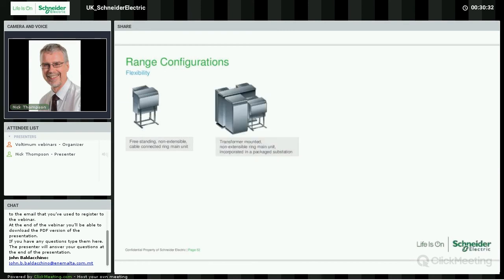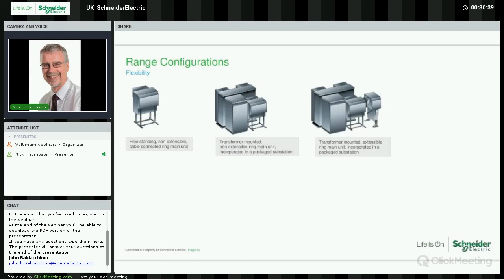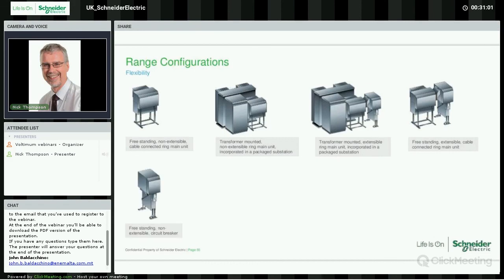cable connected onto the circuit breaker. There is the very popular transformer mounted, and this is showing a unit substation, and then there is also the extensible version, transformer mounted, but also the cable connected extensible unit as well with a Ringmaster range attached to it. This configuration gives you the benefit of having two feeds off of one point on your ring.